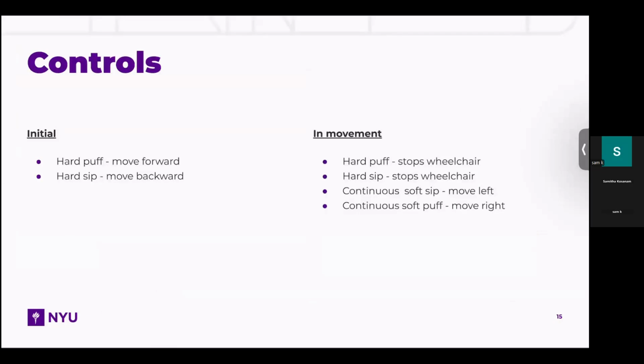And here's an outline on the basic controls when using Sip and Puff with a wheelchair. An initial hard puff will enable the wheelchair to move forward, while a subsequent hard sip will stop the wheelchair. On the other hand, if we begin with an initial hard sip, that will enable the wheelchair to move backward, while a subsequent hard puff at that point will stop the wheelchair. A continuous soft sip or soft puff enables the wheelchair to move left or right respectively, depending on how long the user blows into the tube.